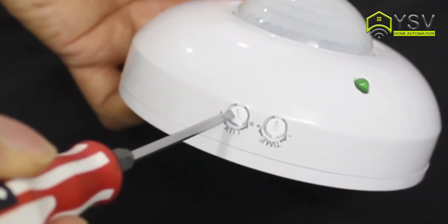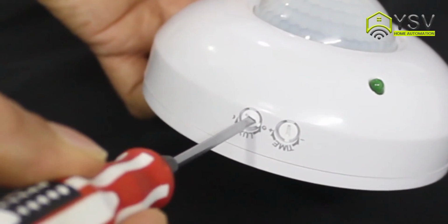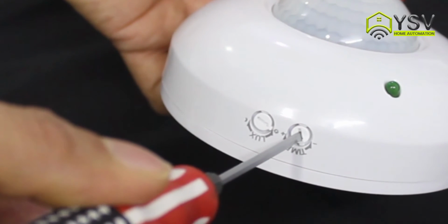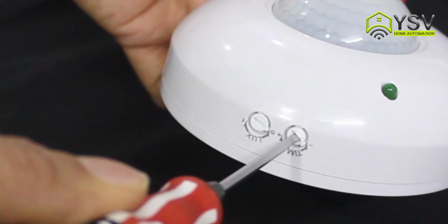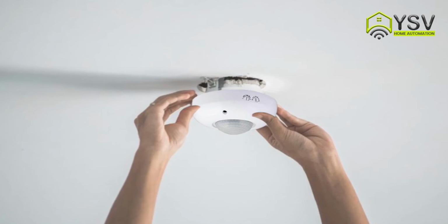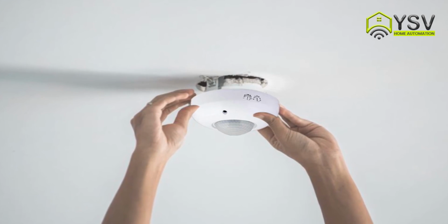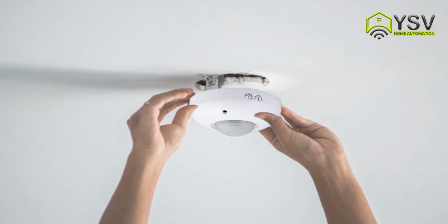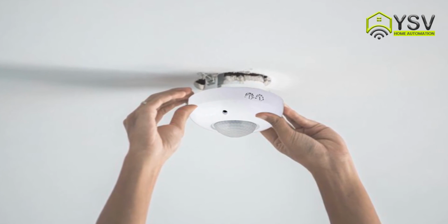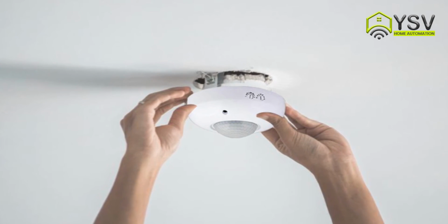Adjust the time for the lights to run along with the lux motion sensitivity before closing the motion sensor. Once you are done connecting all the wires, carefully fix the wall plate at the desired area with a screwdriver and close the sensor with the wires connected to it.